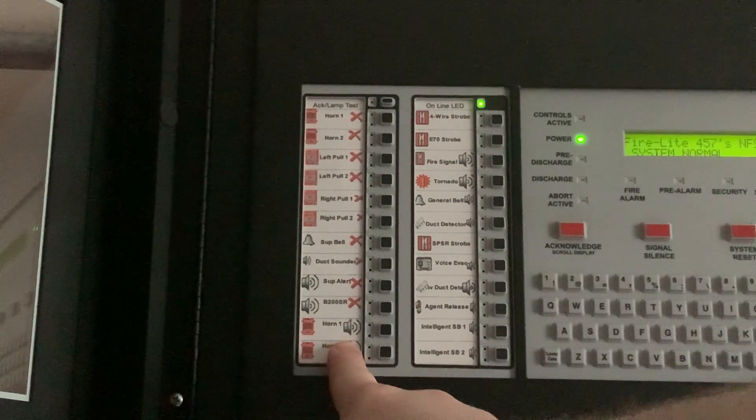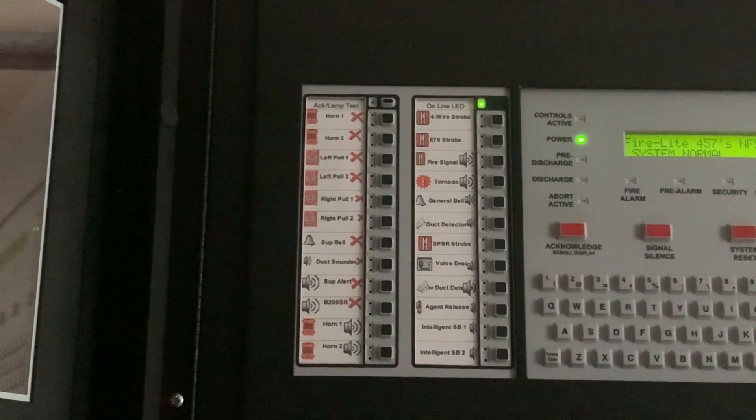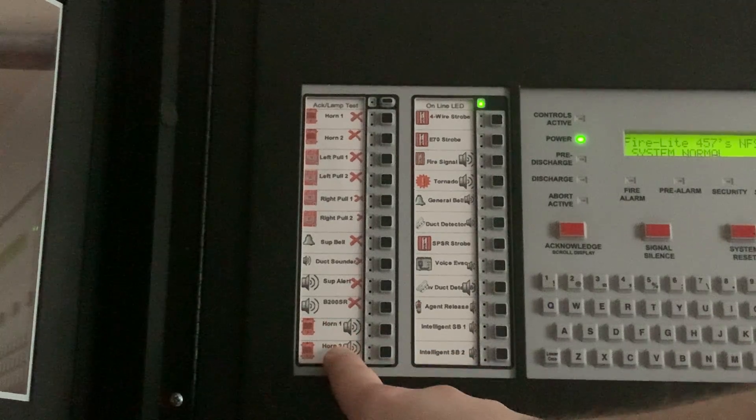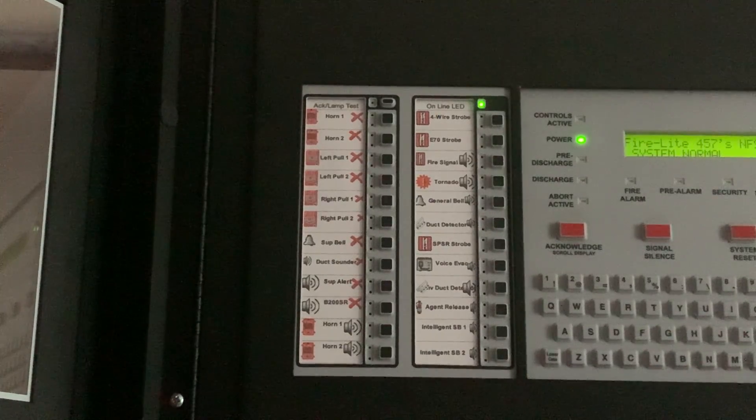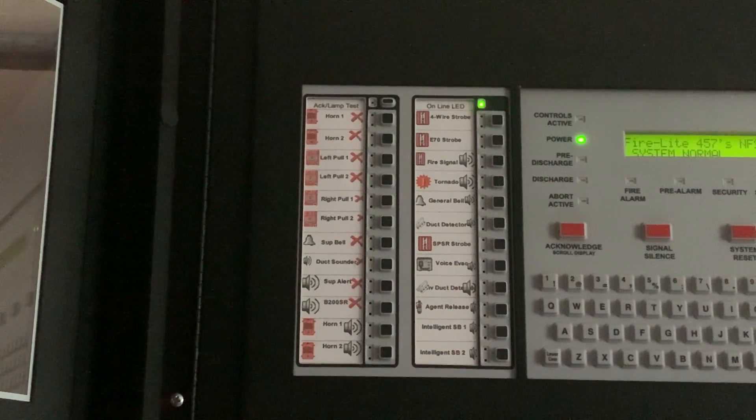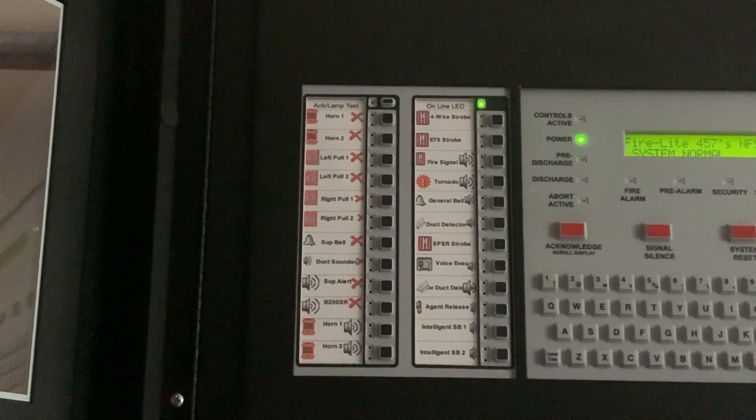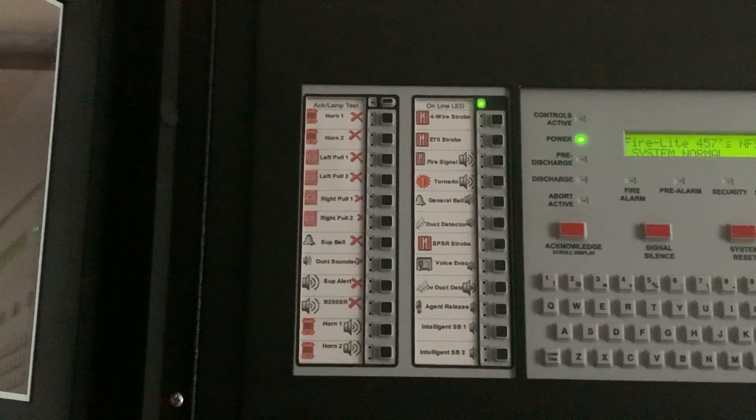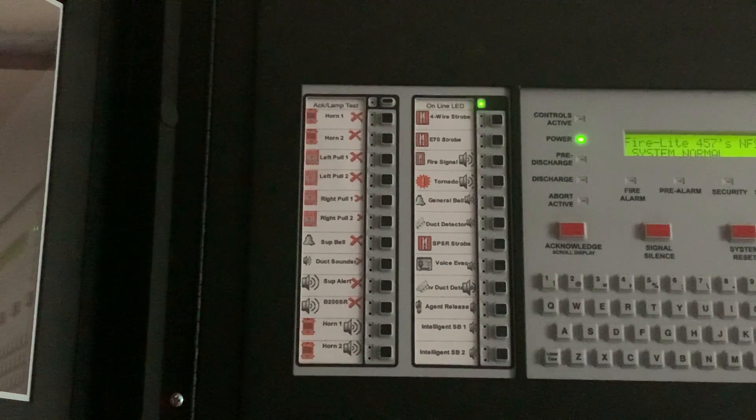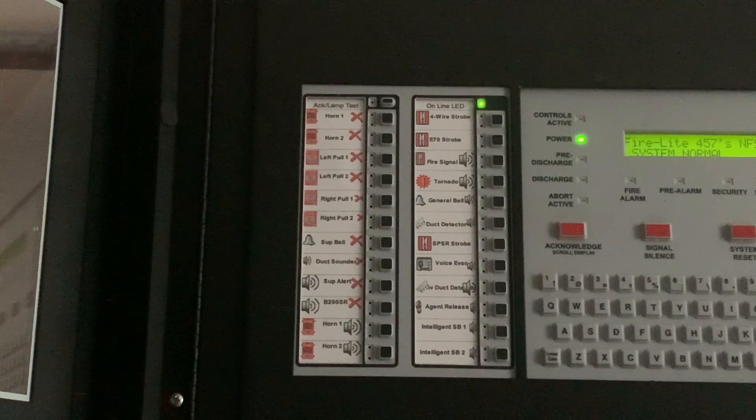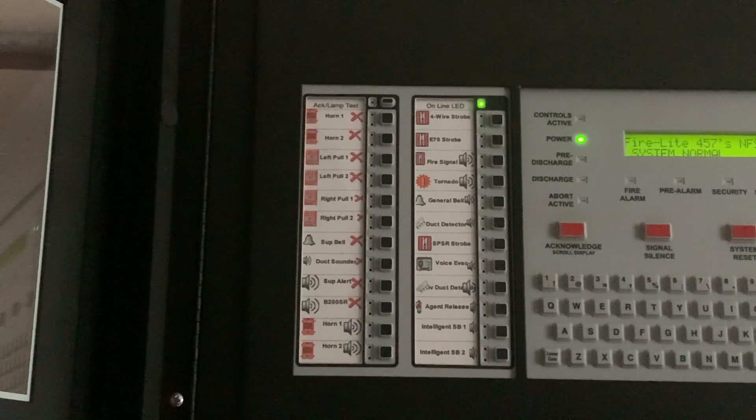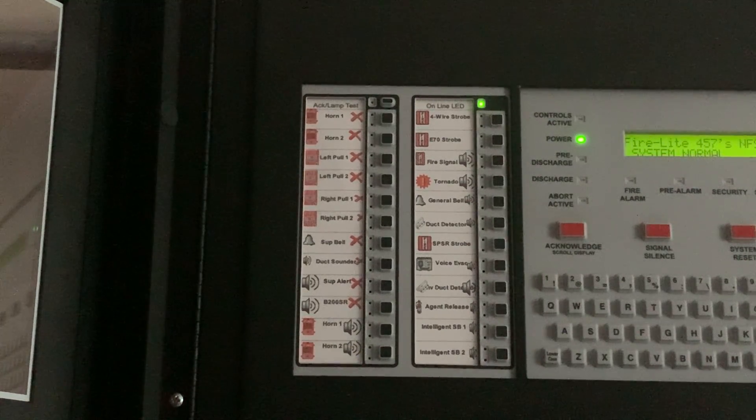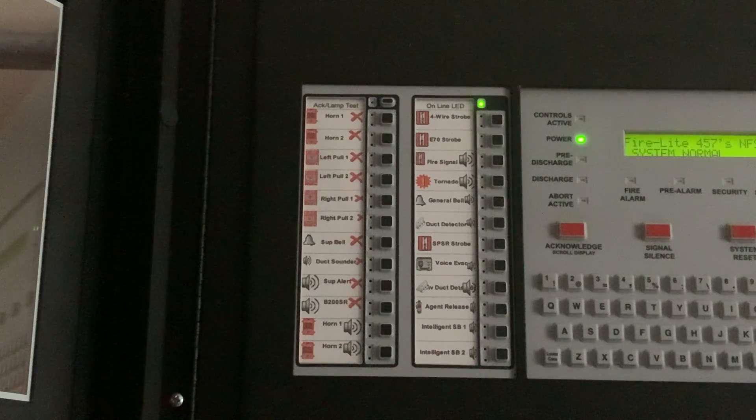And these down here with all the horns and such like that, those are control switches. And I will not be going over activating NAC1 or NAC2 in this video because those devices were recorded in another video for a system test, and I did not want to spoil it for anyone. What if you wanted to activate general zones using the ACM, which would activate all the outputs in that zone? Well, unfortunately, you can't do that. So you can only activate NACs, control, and relay modules separately.